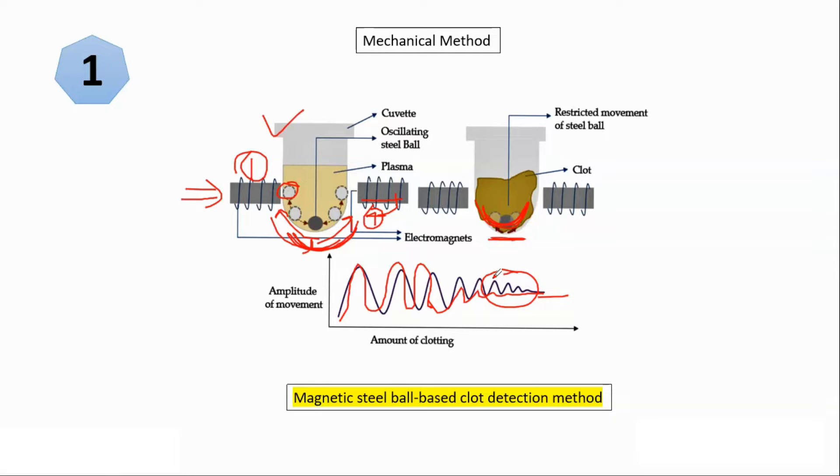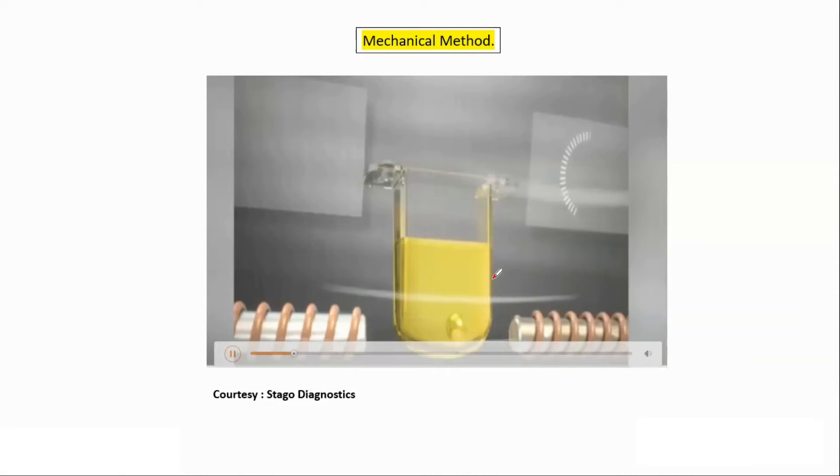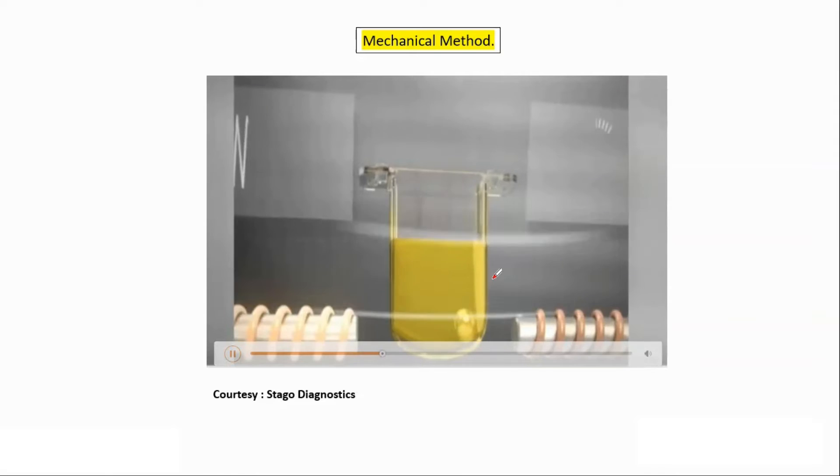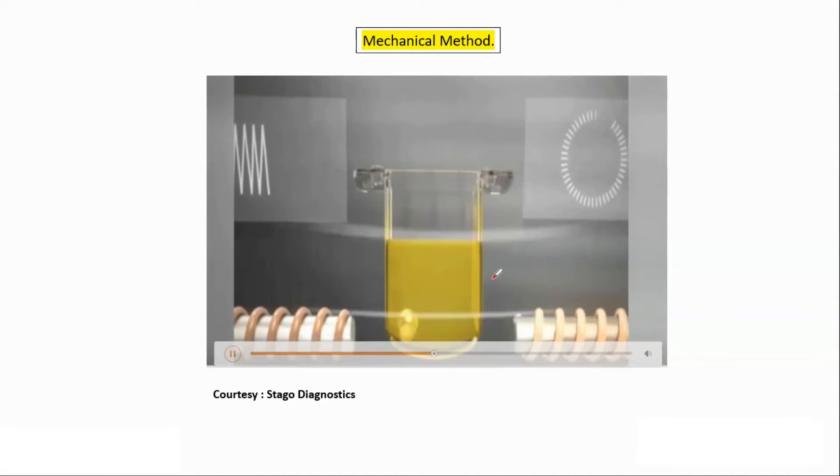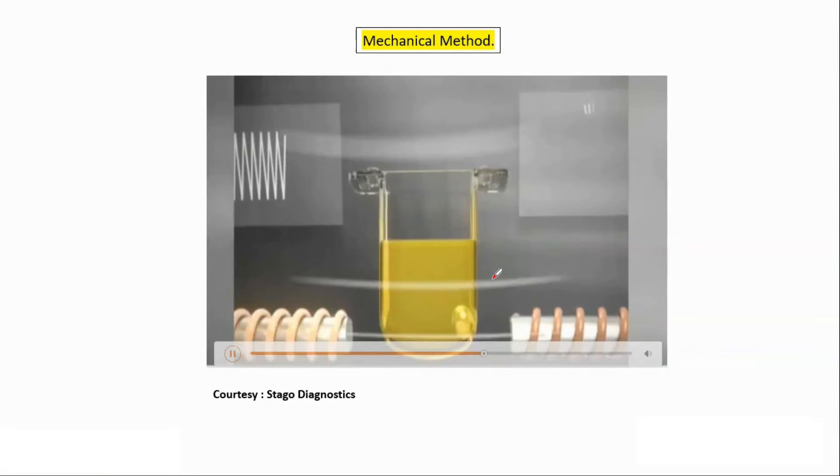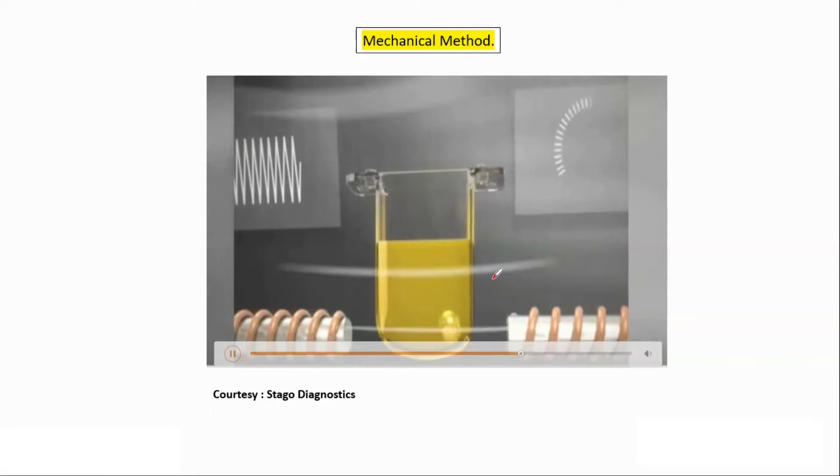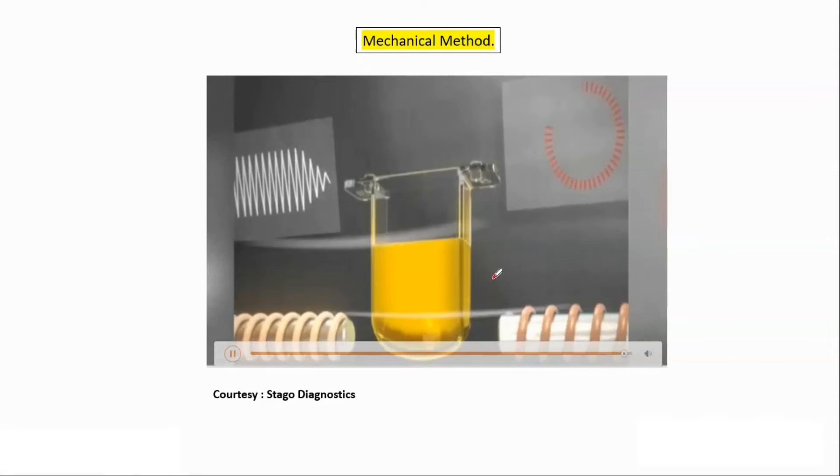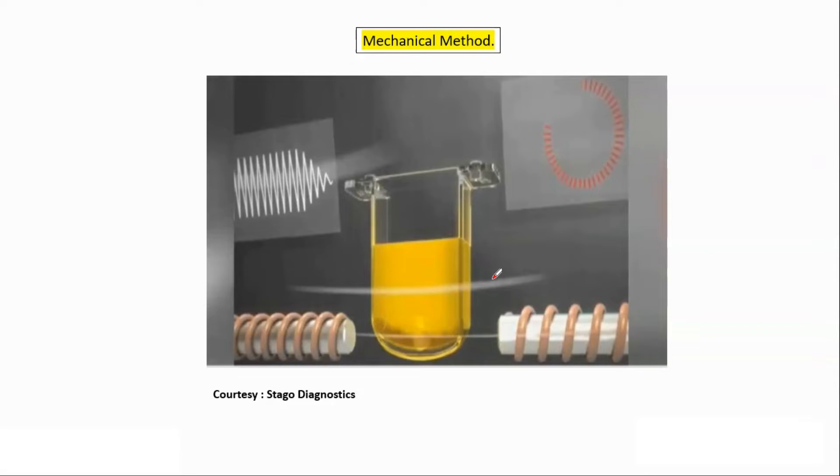So here for better understanding I will show you a video. You can see one time one magnet is activated, ball is moving on that side, and again alternately these magnets are activating, deactivating, and ball is moving as per situation. But as soon as clot gets formed, then chronometer stops. So as soon as clot got formed, then range of motion will be diminished or minimal and clot is detected by the sensors inside it and we will get the reading in seconds.